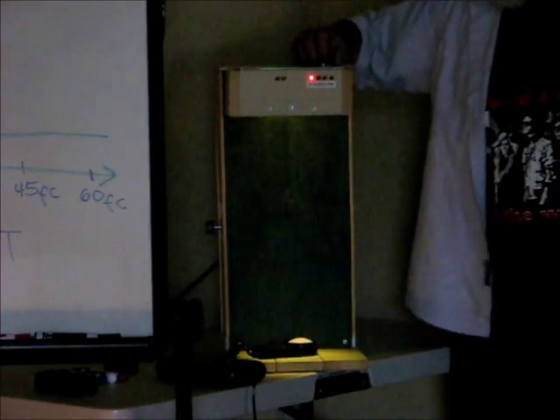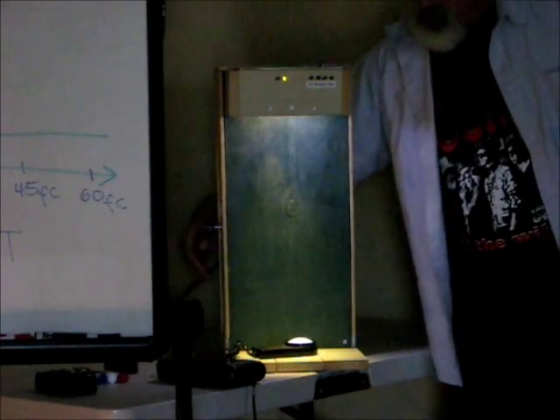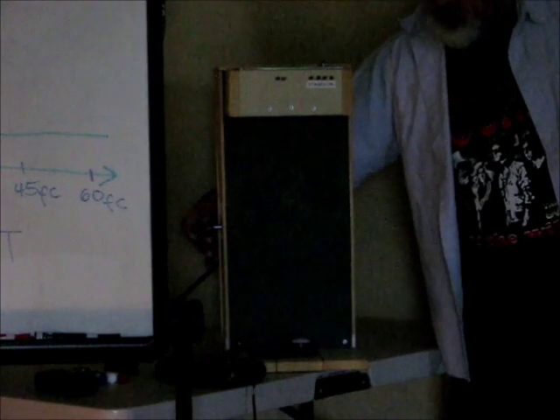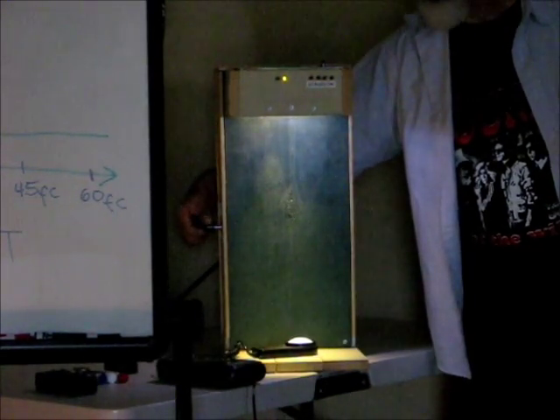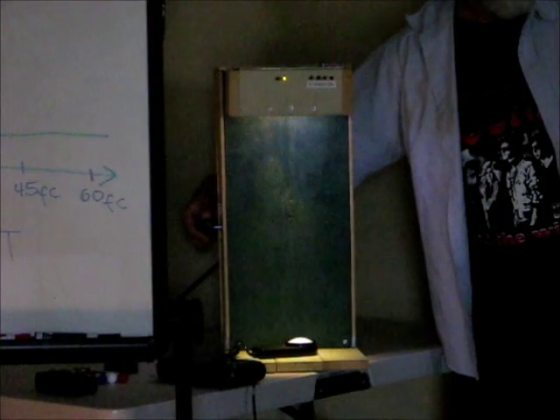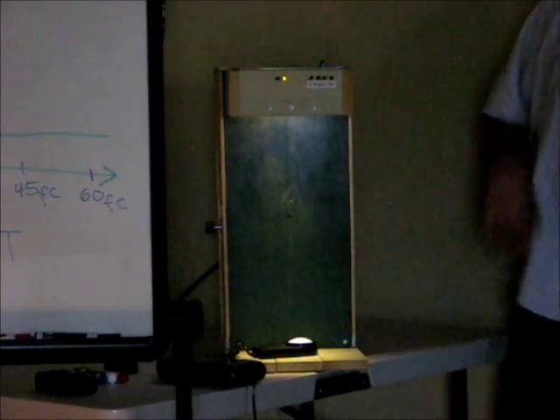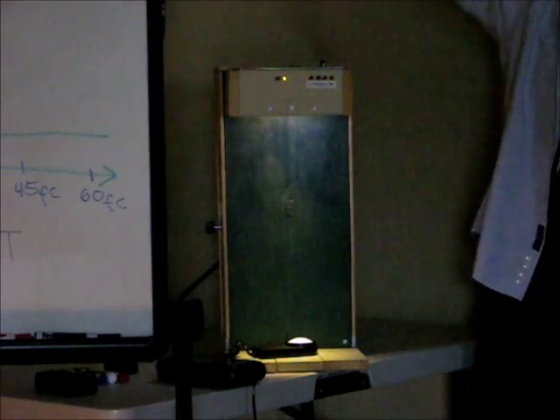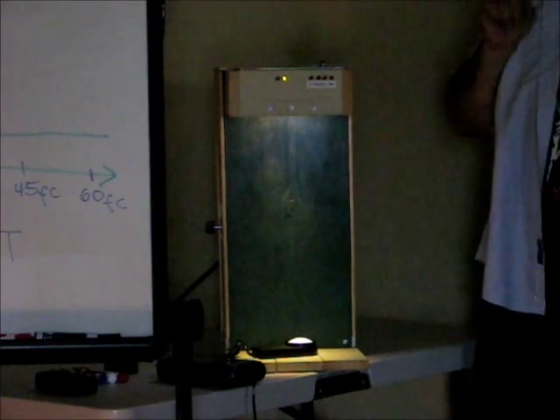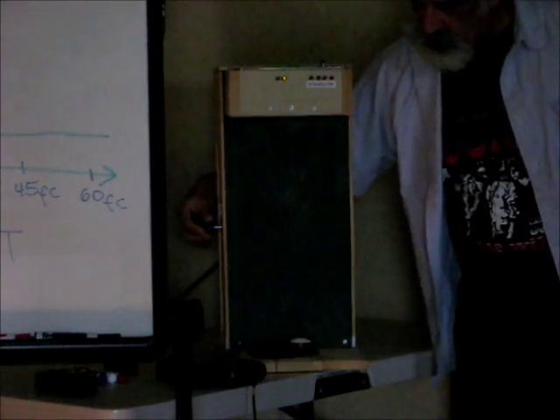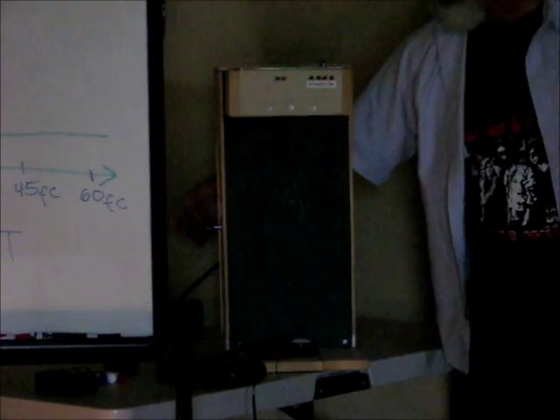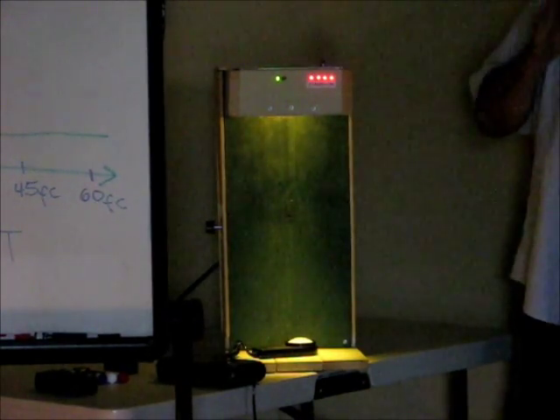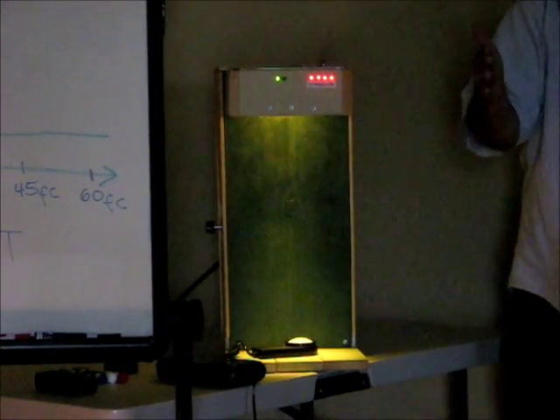I have a knob on the side that adjusts the daylight in the space up and down. Now this is an open loop system. In fact, we don't even know where the sensor is. We'll say it's three rooms down in an atrium, 30 feet up. But we know we're going to get a ton of light in this location. So what we're going to do is just go ahead and record the illumination in the space from no daylight conditions to full daylight conditions.